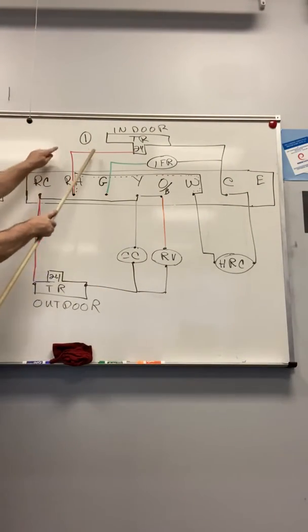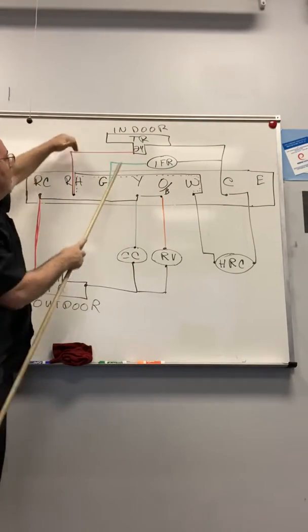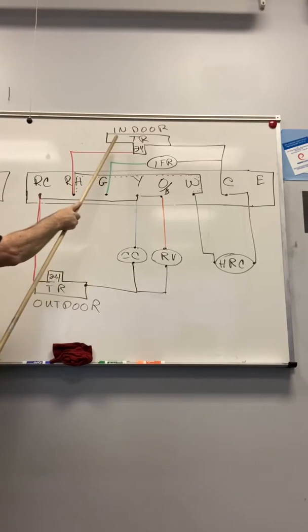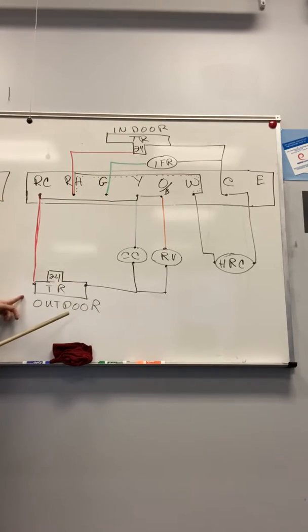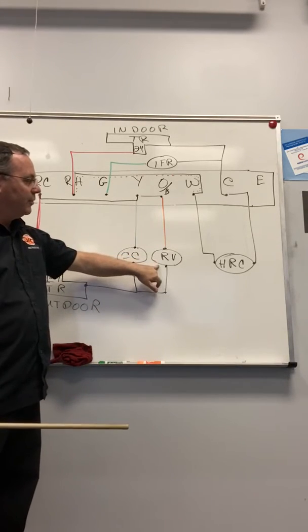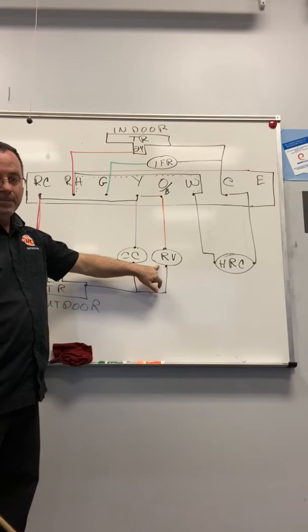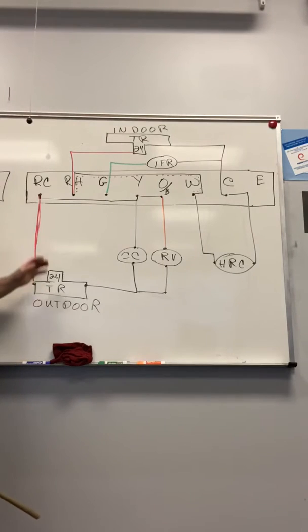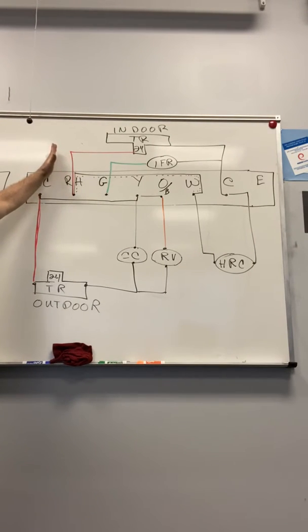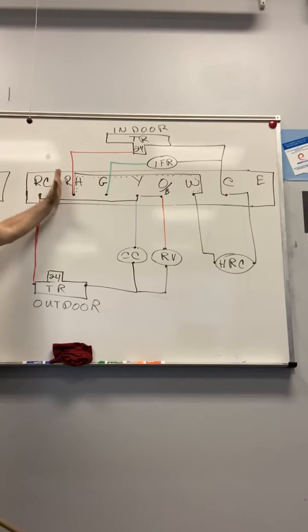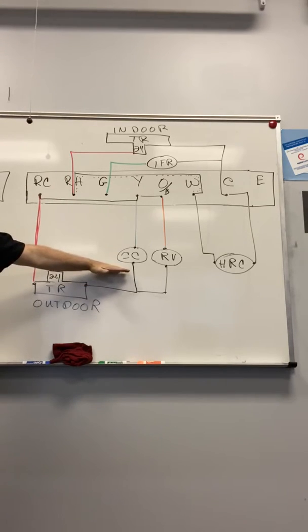So let's look at this now. Here's an outdoor transformer, indoor transformer. And here is my outdoor transformer. We know this one's going to be for the contactor and the reversing valve. Okay, outside. The indoor will have to be for what? The indoor heating system, because the outdoor is for the cooling system.